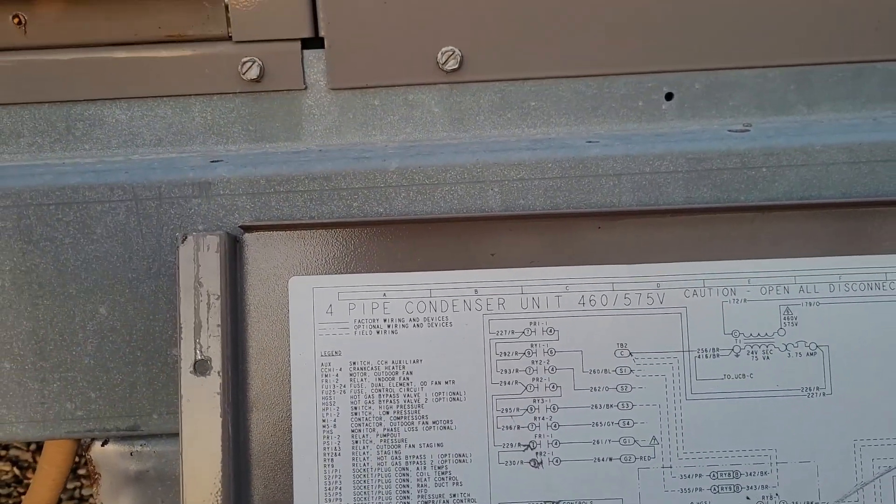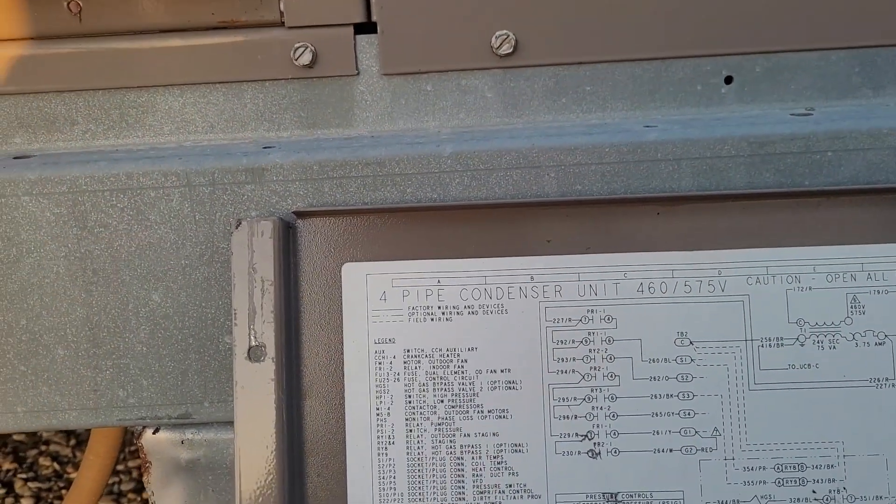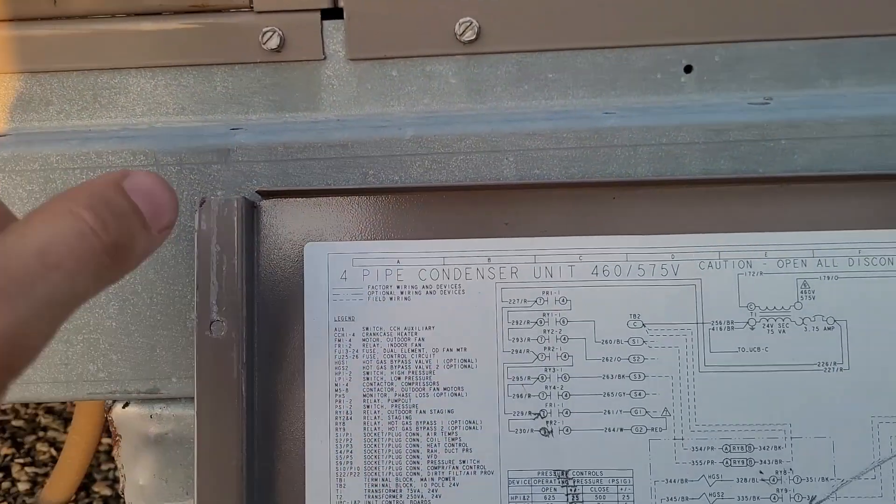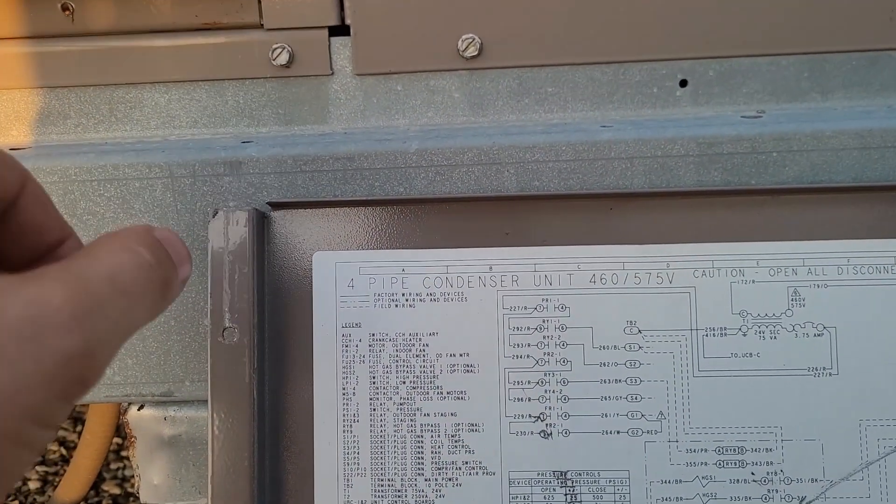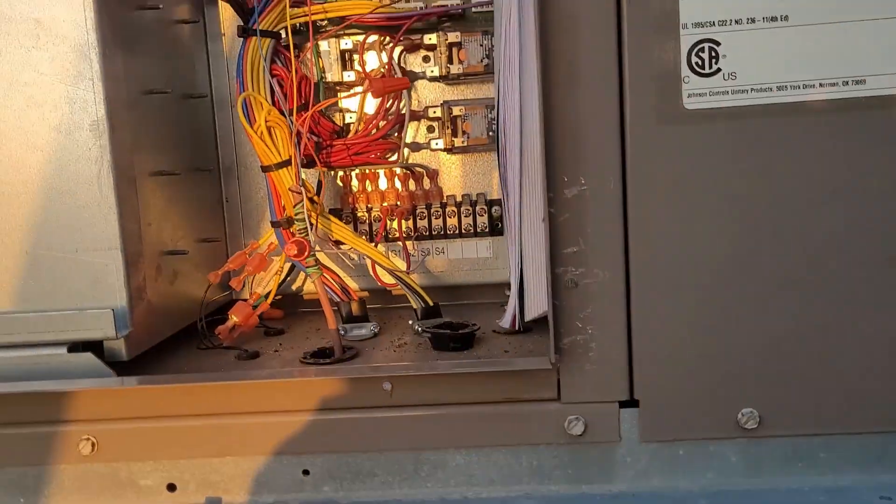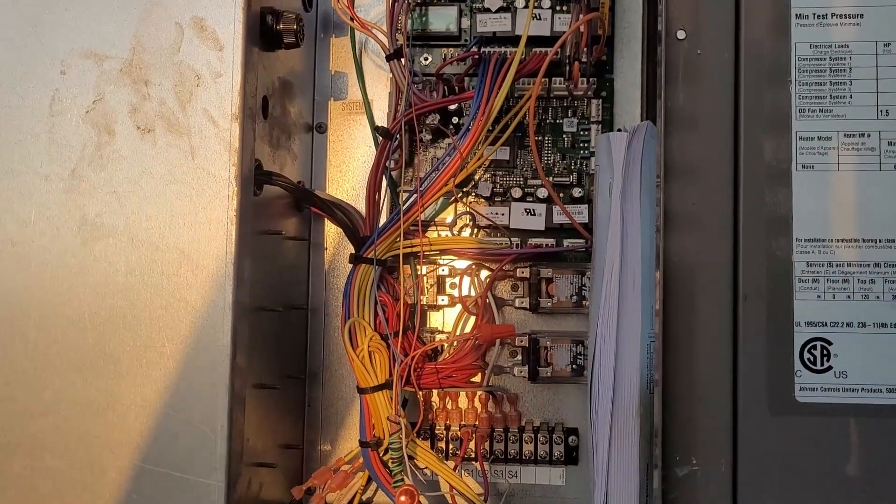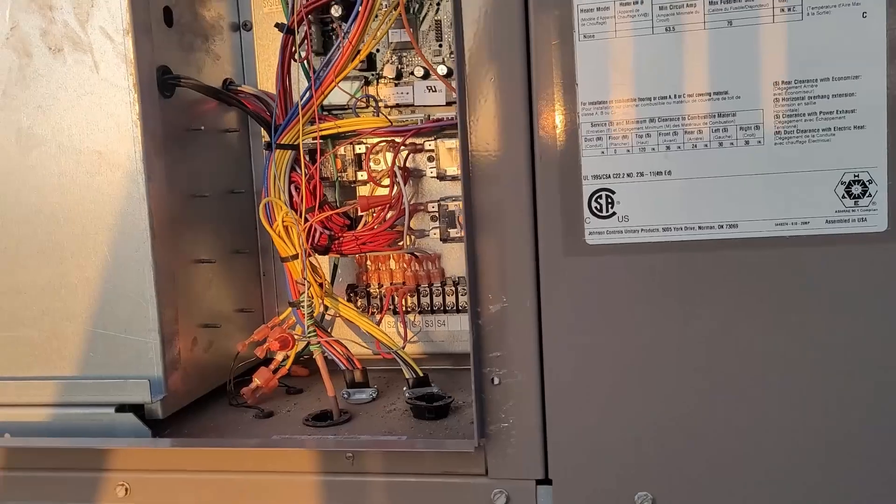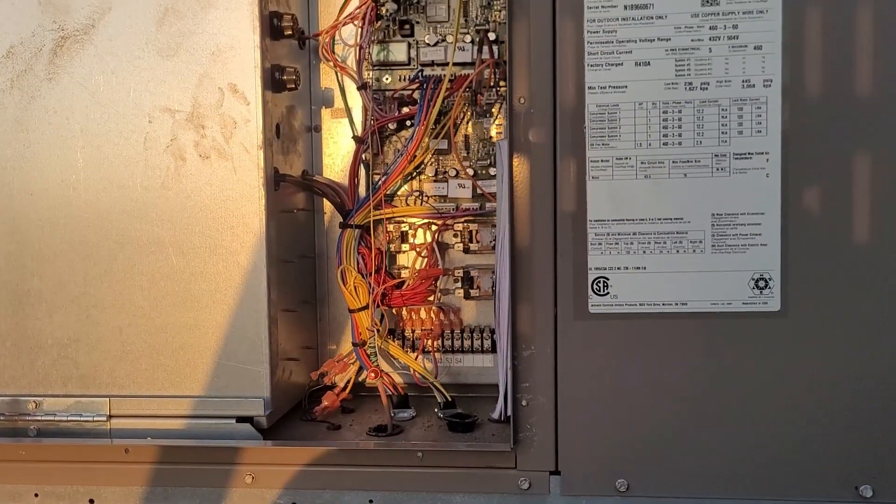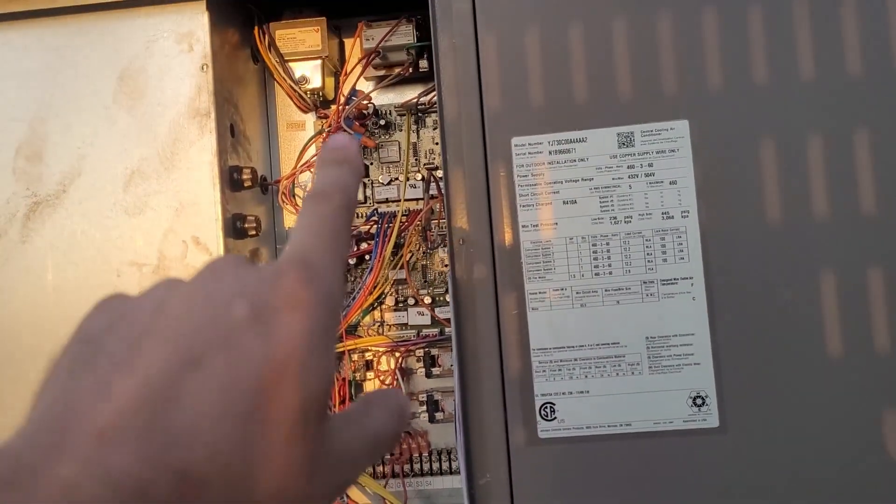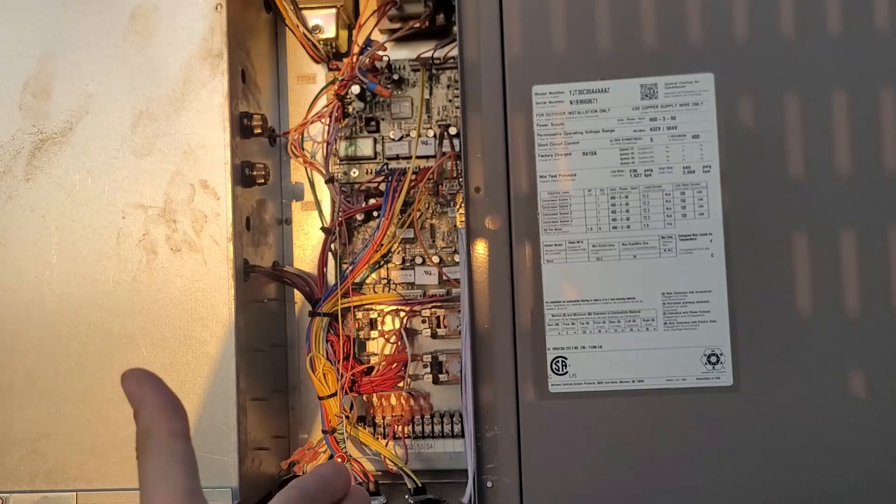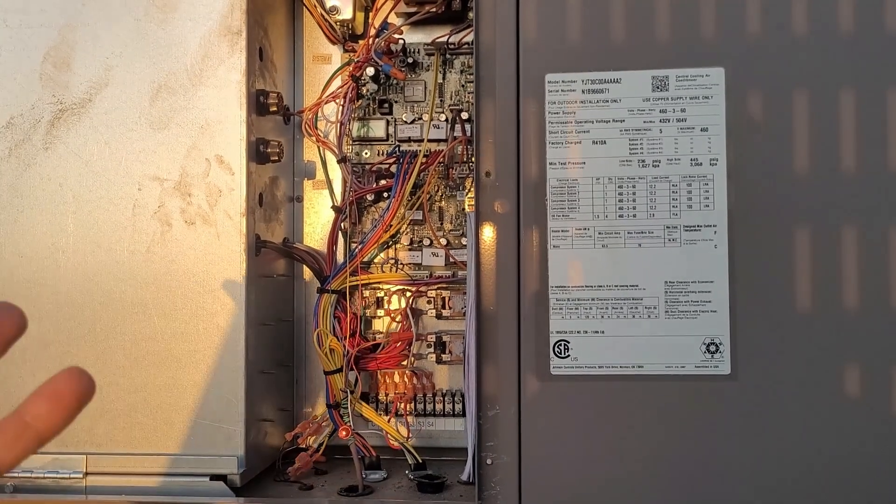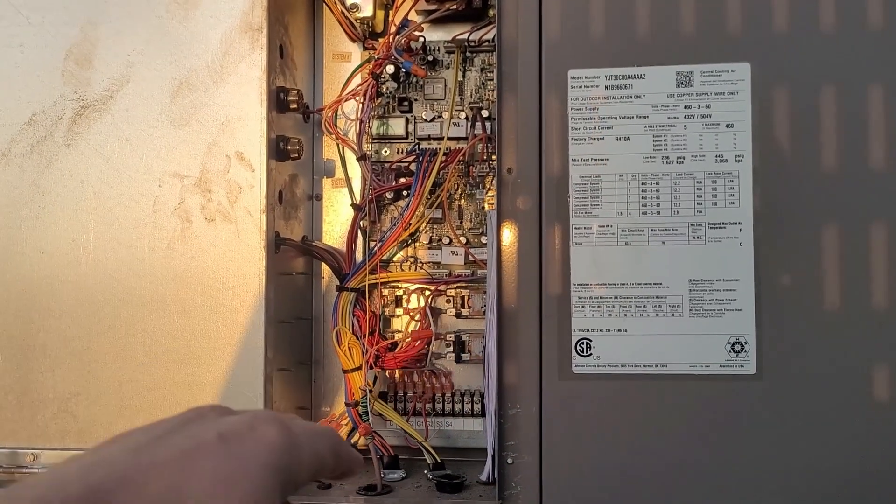But what happened was, the control company that was here before us tied in S1 and S3 with the Y1 and Y2 calls. So as soon as you had a call for Y1 from your controller, the call comes up to the board. The board says, oh, I need to turn on S1 and S3 so that I can get my stages of cooling going.